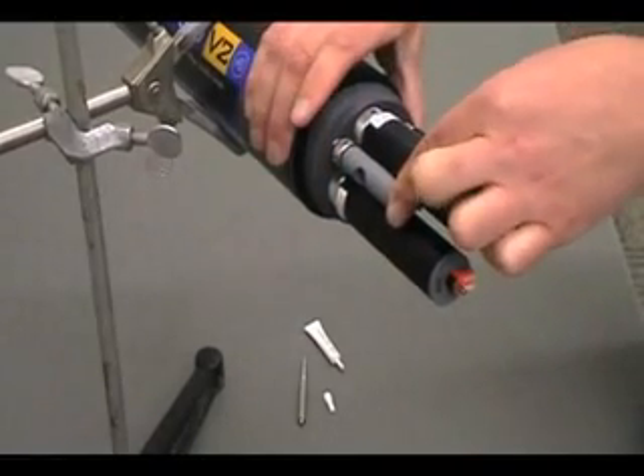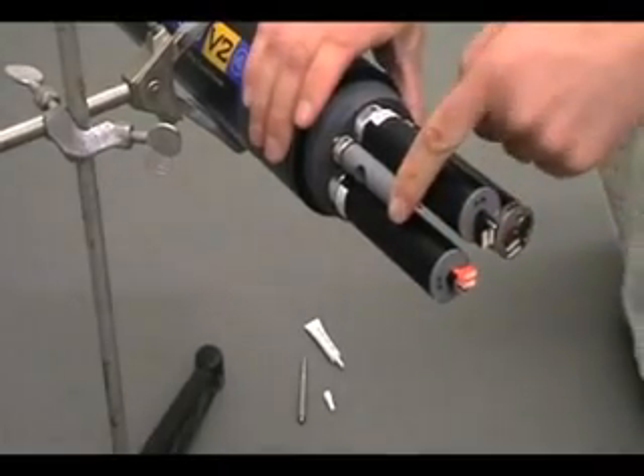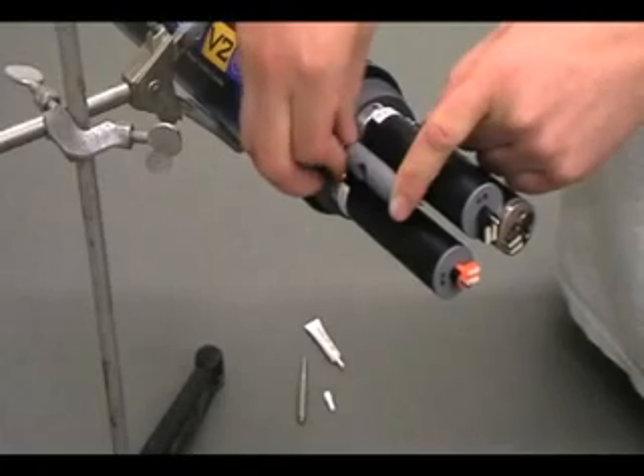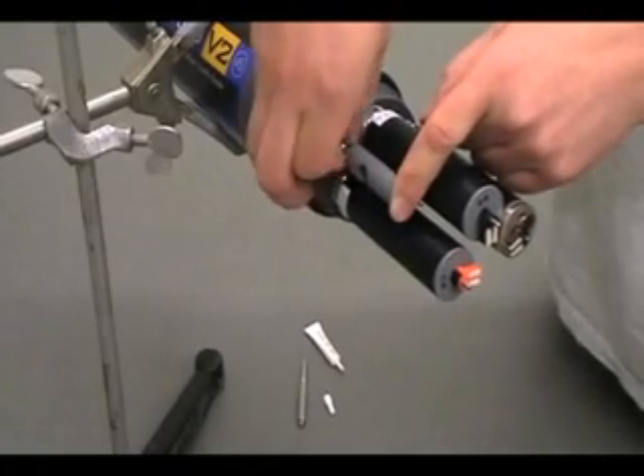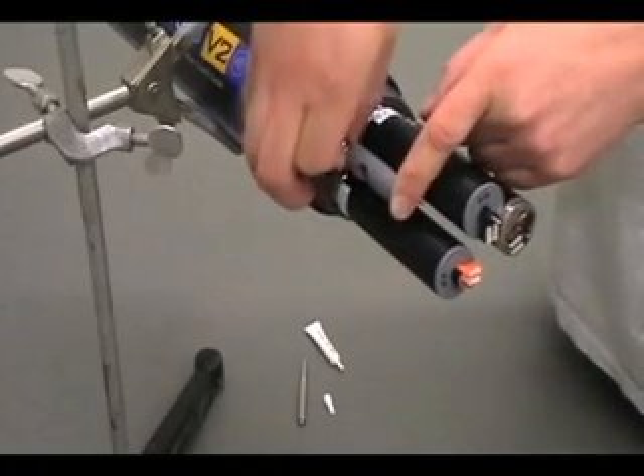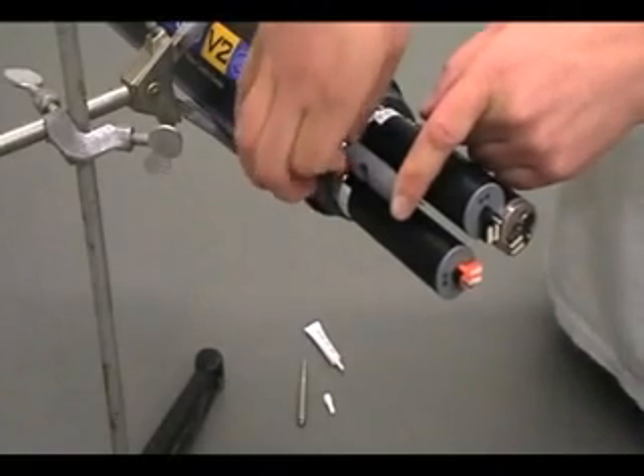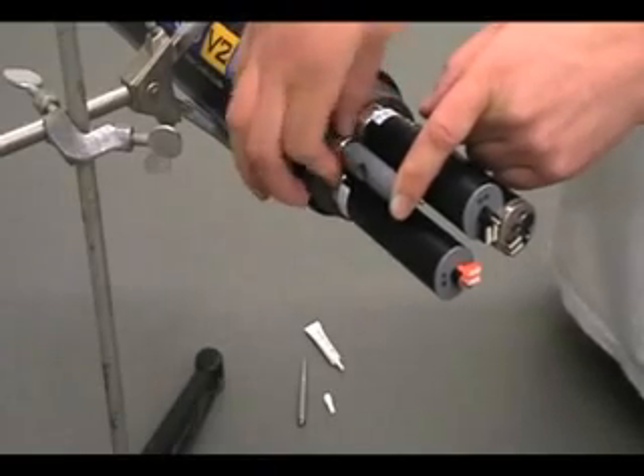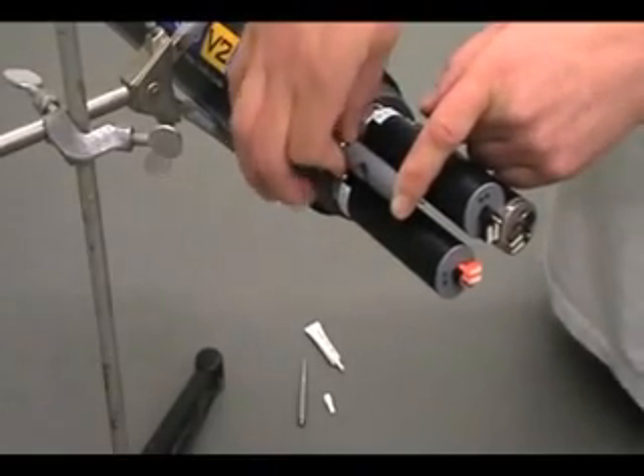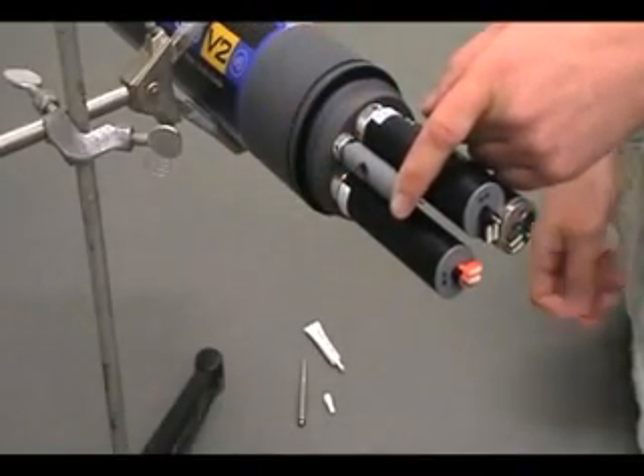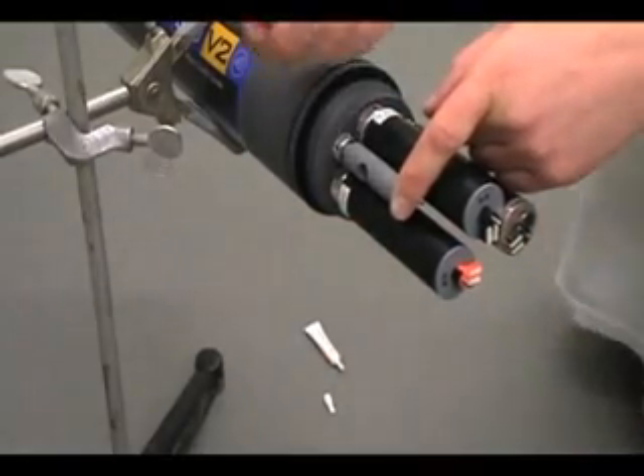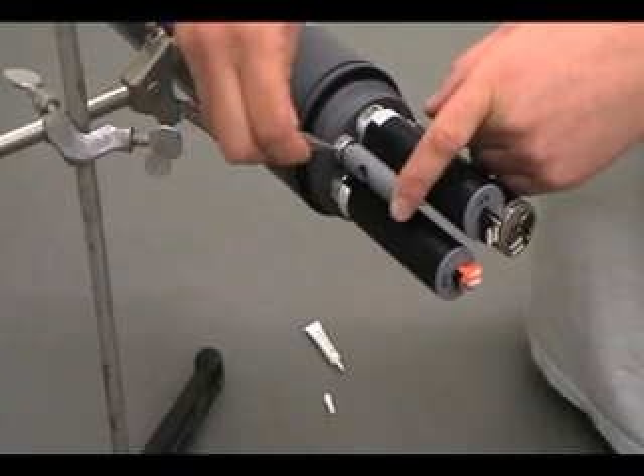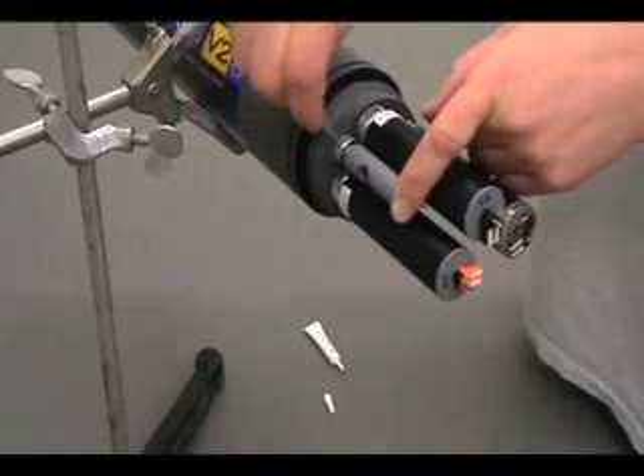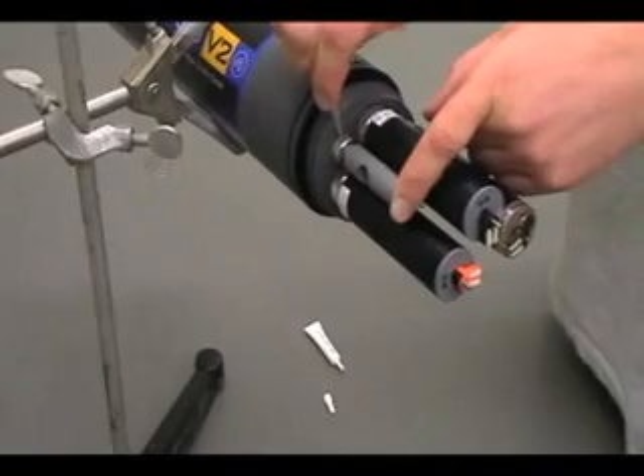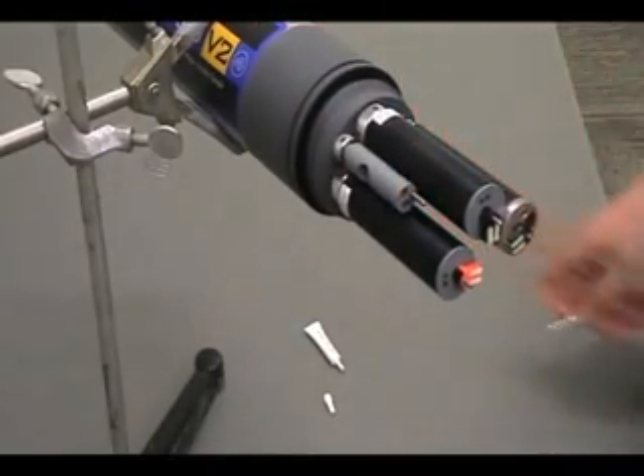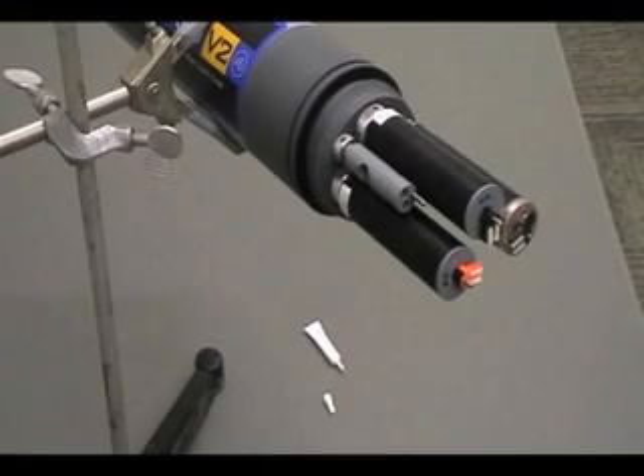Push the sensor inward so that it seats in the port snugly. Slowly finger tighten the nut down toward the bulkhead. During this step, be careful not to cross-thread the nut. If you meet resistance while finger tightening, stop, back out, and begin the process again. Use the long end of the installation tool to tighten the nut an additional quarter turn until snug. Do not over-tighten. When tightened properly, there should be no space between the nut of the regular sensor and the body of the bulkhead.